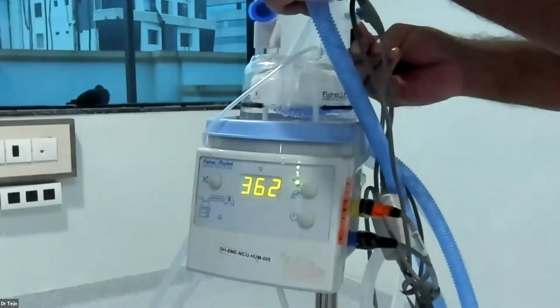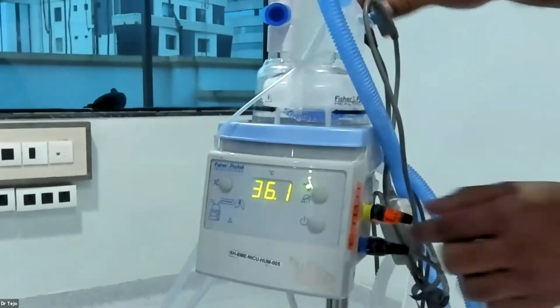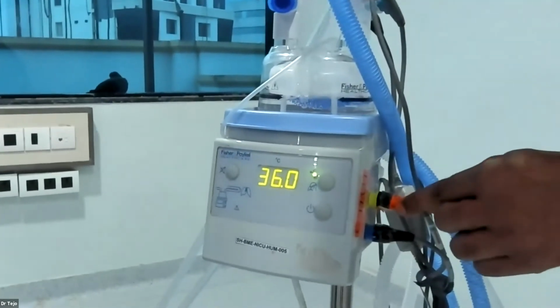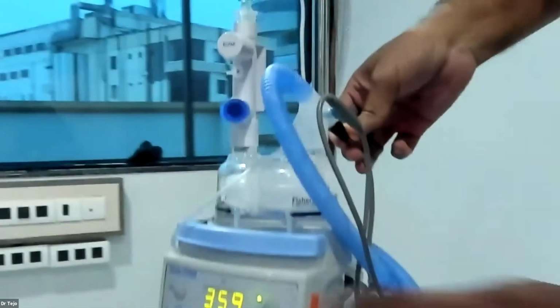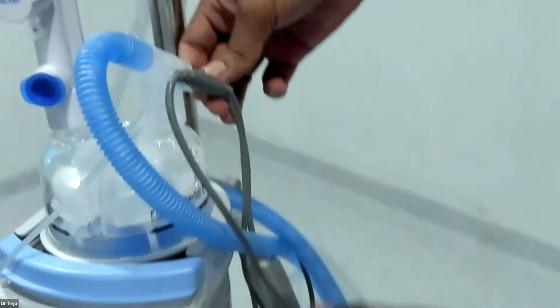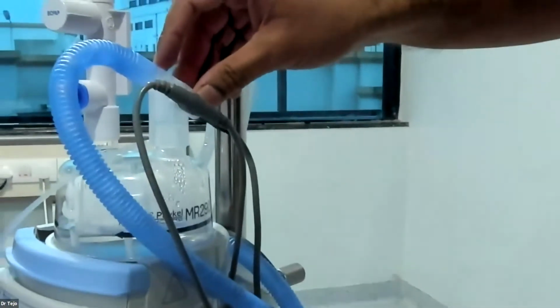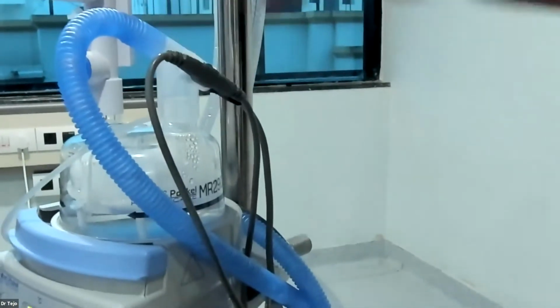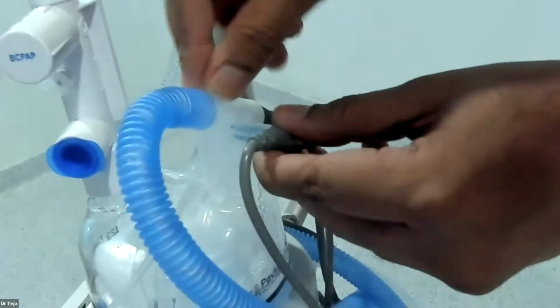And if it is disconnected or malfunctioning, then the alarms will be raised. So either the heater wire adapter connector or the heater wire adapter, these 2 will give alarms simultaneously, together. If it is not connected properly, or if it is malfunctioning, then it will give the alarm. So another one is the chamber probe.